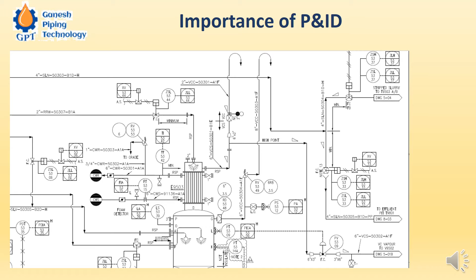Now we have zoomed in further on this line, and we will see that it has an RSP. This is a removable spool piece. Why this removable spool piece? That is why there are two flange joints. If this equipment has to be removed for some maintenance purpose, it may swing here and there, so this RSP spool piece will be removed and then the equipment can be lifted by crane. So it is a safety for this piping system.